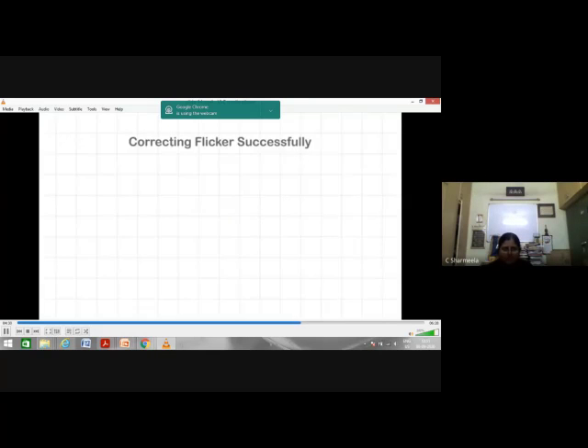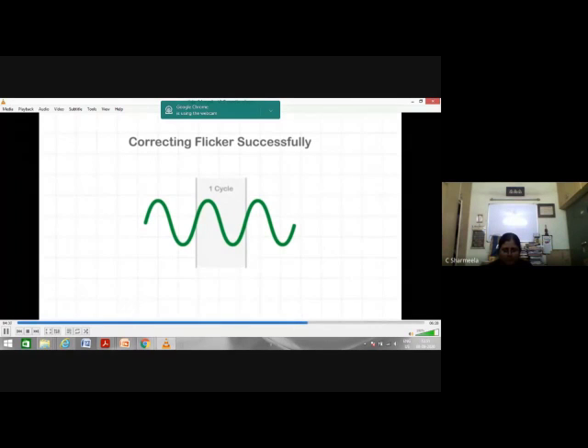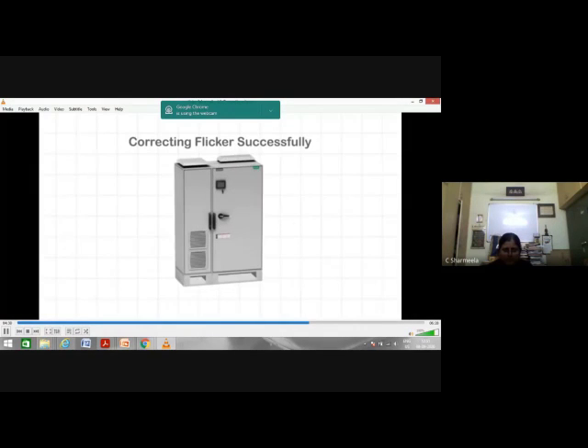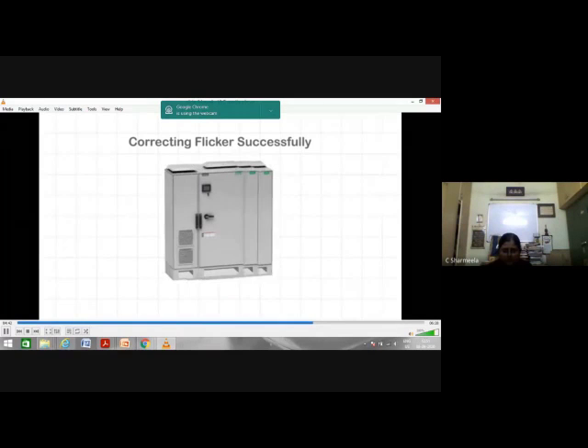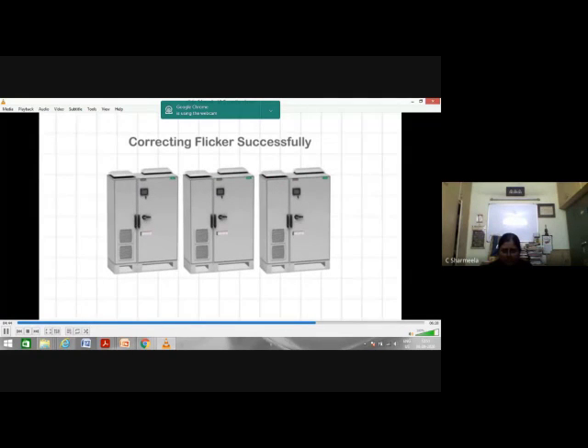To be successful in correcting flicker, you must inject the right amount of reactive power within one electrical cycle. This makes the AccuSine ideal for the job because it's scalable. You install the number of units you need in parallel, and it can inject kVAR within 1/4 of a cycle, 4 to 5 milliseconds.